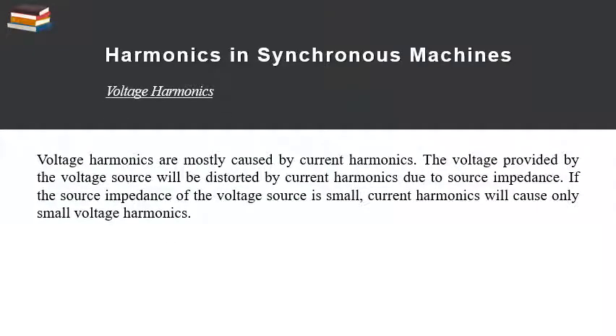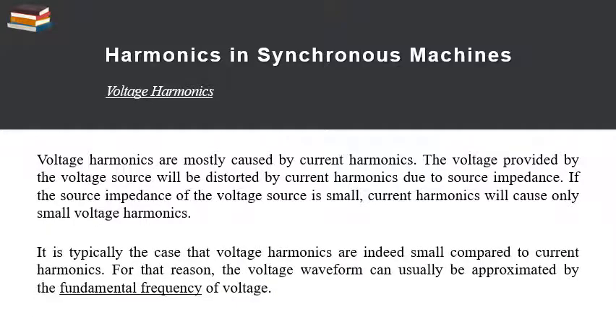The next topic is voltage harmonics. So the voltage harmonics are mostly caused by current harmonics. The voltage provided by the voltage source will be distorted by the current harmonics due to source impedance. If the source impedance of the voltage source is small, then current harmonics will cause only small voltage harmonics. It is typically the case that voltage harmonics are indeed small compared to current harmonics. For that reason, the voltage waveform can usually be approximated by the fundamental frequency of the voltage.